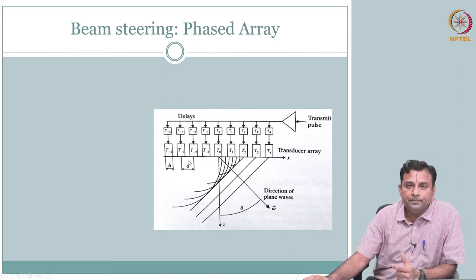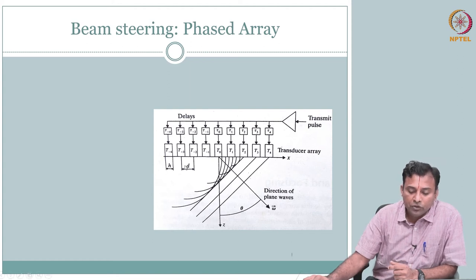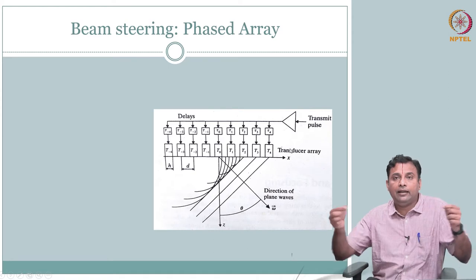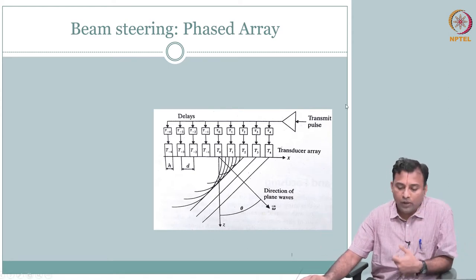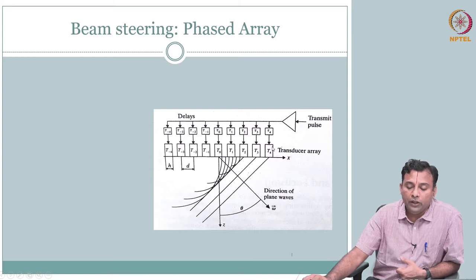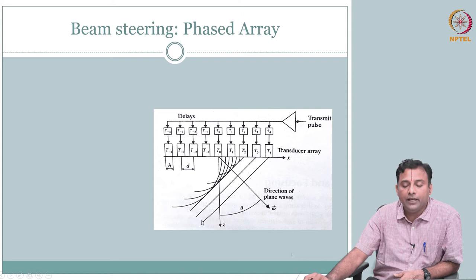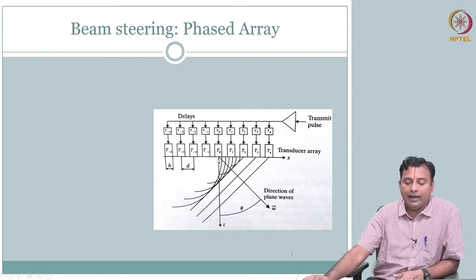Pitch is an important parameter when you choose a transducer and design your beamforming. Pitch is d. You have the z direction and x — the length direction of your transducer. The transmit pulse can be given to each transducer element separately with its own time delay. So if we take a situation where we are sending a plane wave in a particular direction theta, the plane wave is now travelling at an angle theta.